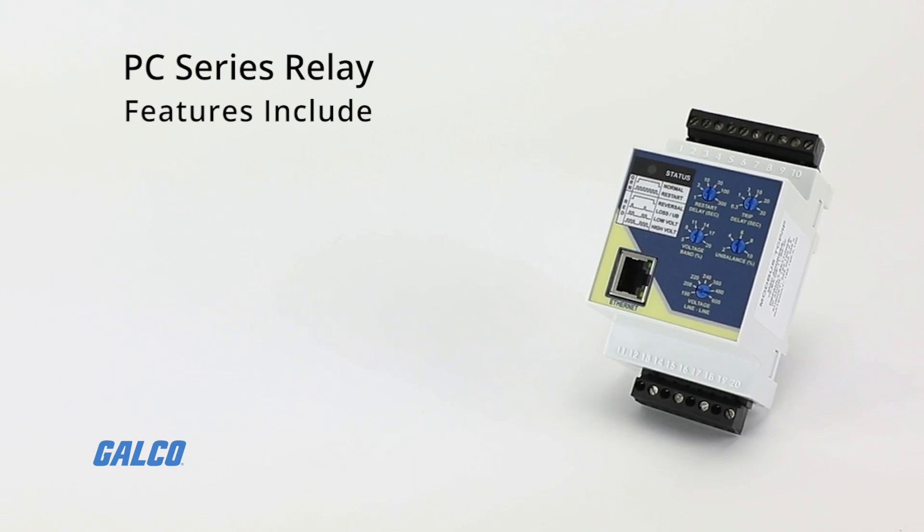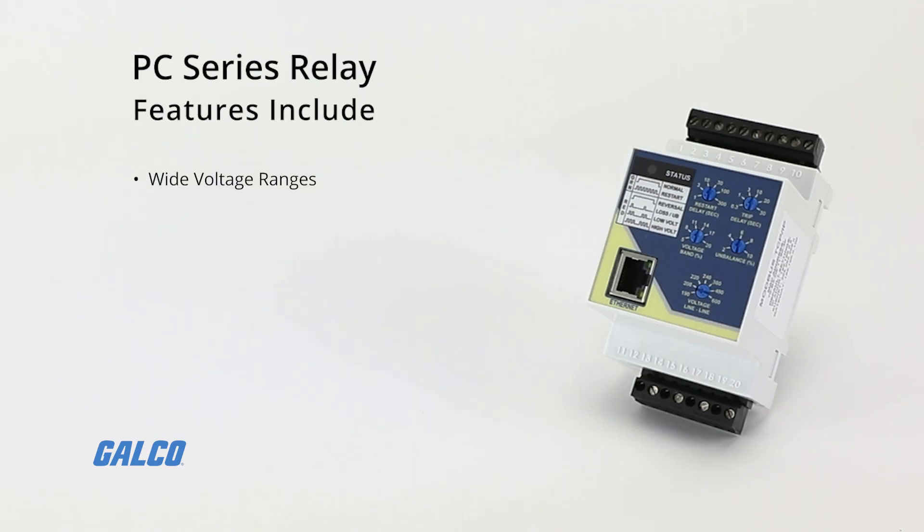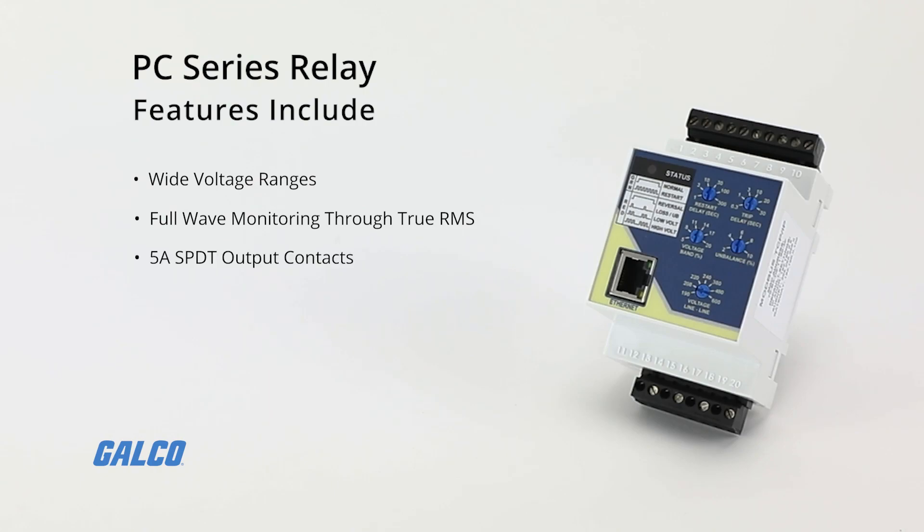Other features include wide voltage ranges that cover more global applications, increased and accurate full-wave monitoring through true RMS voltage measurement, 5-amp SPDT output contacts, RJ45 Modbus connector, and full connection speed of 10 to 100 megabits as well as half-duplex connection speed.